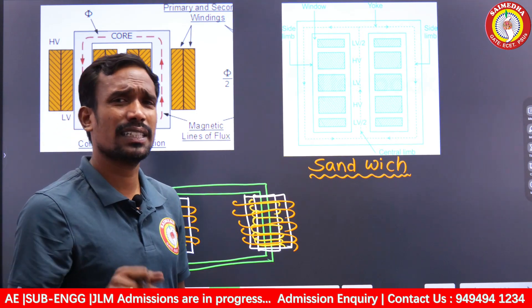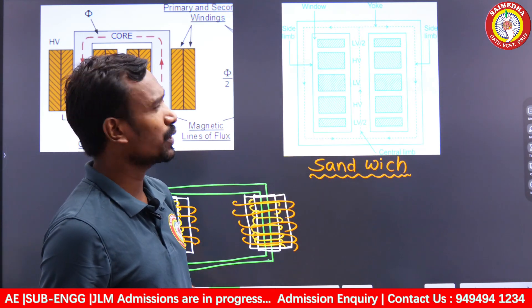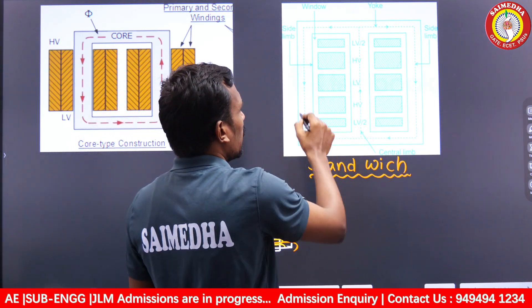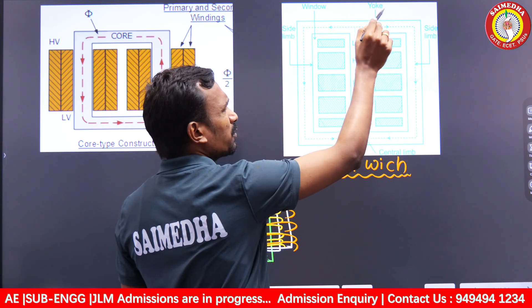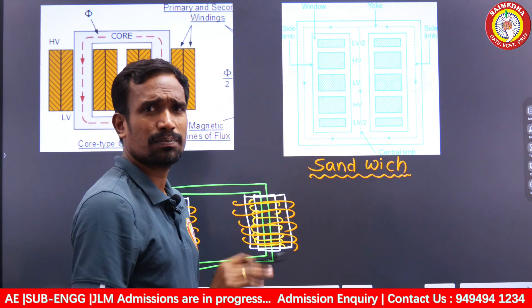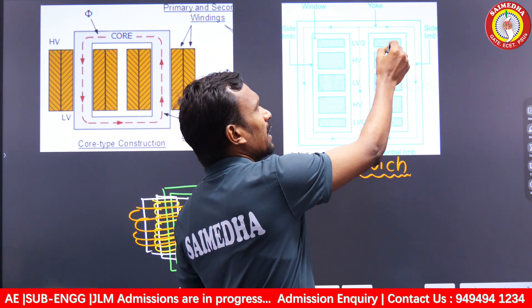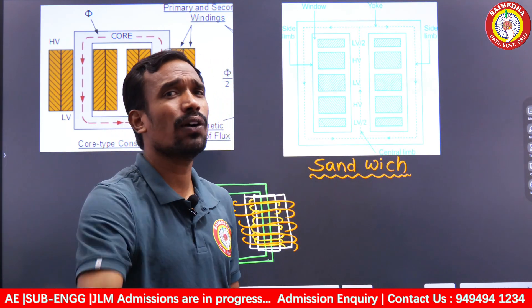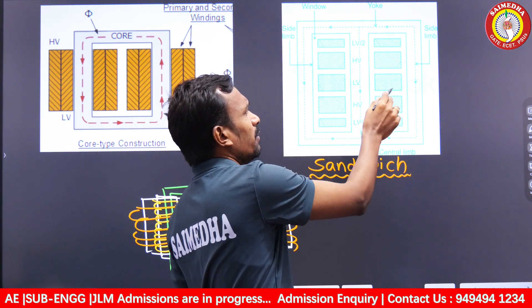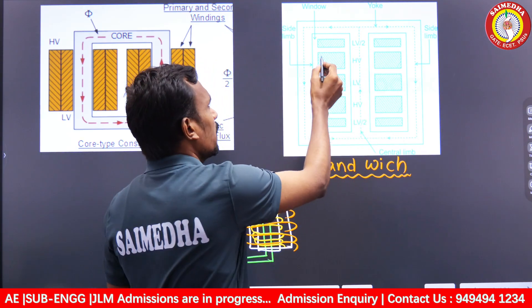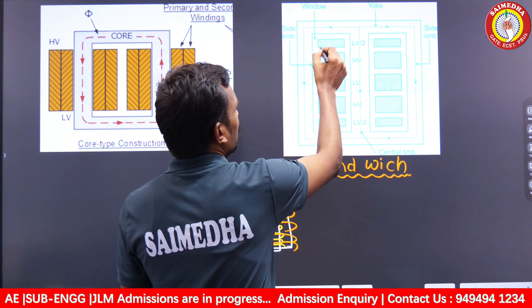For sandwich winding, the middle limb and two side limbs carry the windings. It is always preferred to place LV winding at the ends because LV windings give less leakage flux; HV at the ends gives more leakage flux. The arrangement is LV, HV, LV, HV winding layer by layer, with insulation placed between every layer.